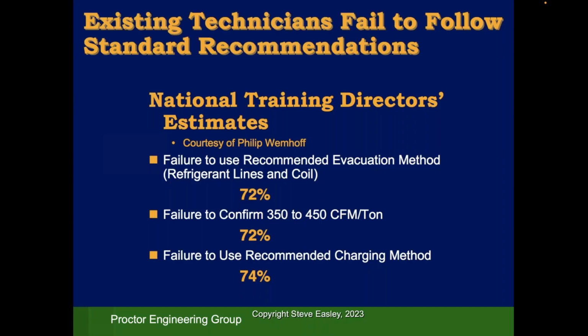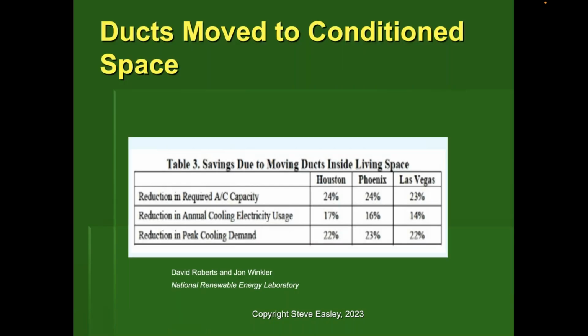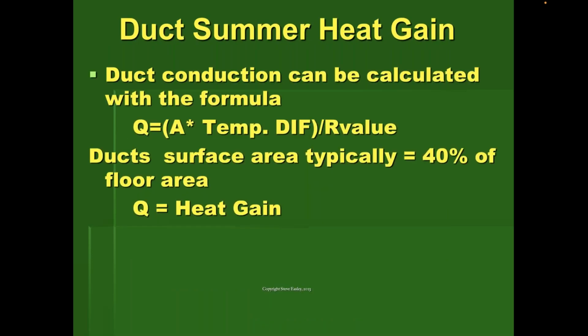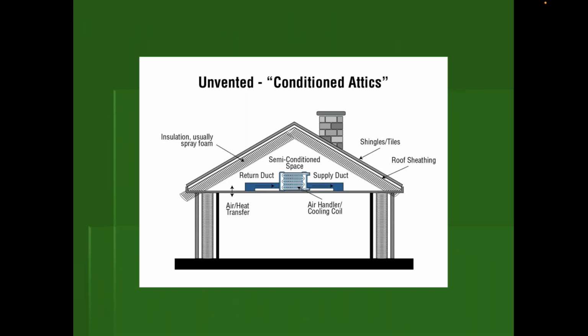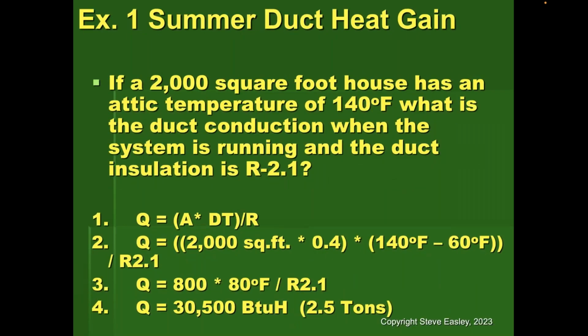In fact, a lot of studies have been done on this and found some of the traditional shortcomings: three-quarters of the time, they don't have adequate airflow. They don't use the proper method for evacuation of refrigerant lines. The failure to use recommended charging methods. All these things are really important. From the same NREL study. So this, for example, here, if we look at the capacity of these systems, my system's going a little nutty there. Bottom line is, when we're looking at the capability of these systems, you could save easily 20–25% or more just by getting installed right.